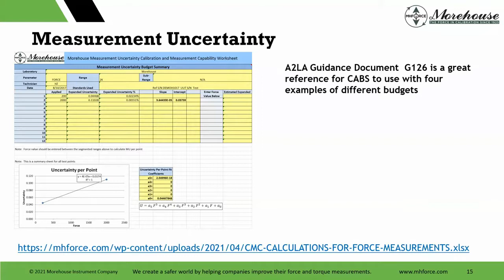When we look at force specifically, types of instruments, and I'm throwing some terminology around there, such as primary standards, this is a tiered system approach. So tier 1, we have primary standards. That's typical no matter what your discipline. And that is like dead weight, and that's what we showed earlier, where we have dead weights. Then tier 2 would be secondary standards, like your load cells, your proving rings. Tier 3 could be even more load cells, crane scales, dynamometers. And then tier 4 ultimately is the testing machine or materials test.